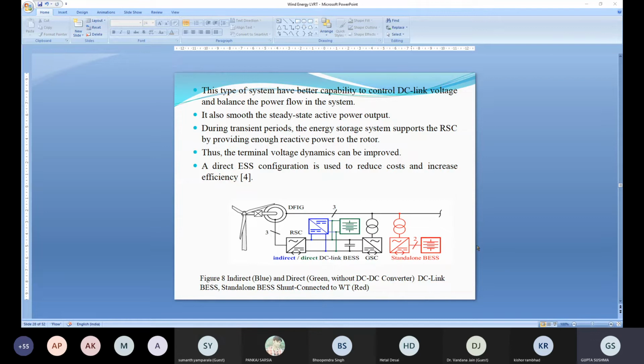And the third one is the standalone battery energy storage system. It is not connected between the RSC and GSC. It is connected standalone. So when there is a grid fault and voltage dip in the grid, this circuit feeds the reactive power so that the voltage will recover fast. So there are three types of configuration in a DC link energy storage system.